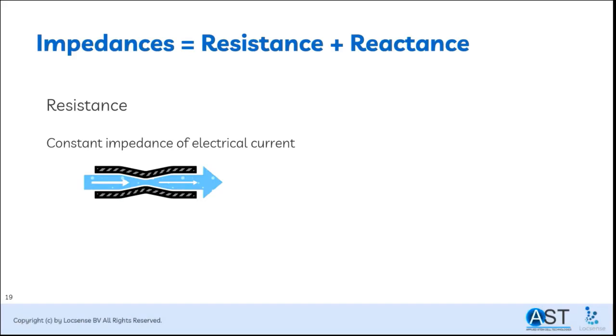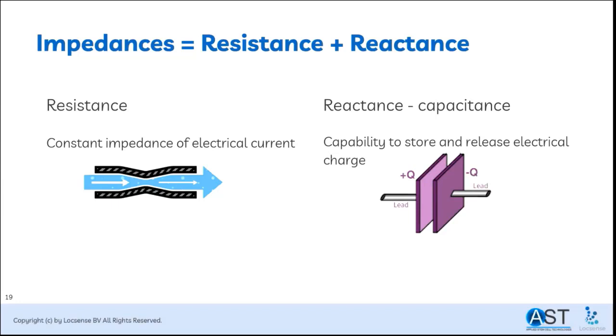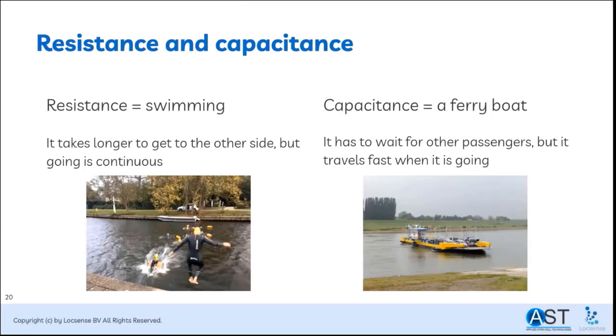TEER can be extracted from the impedance data, but total impedance is more than only TEER — it is the sum of the resistors and the reactances. Resistance is constant and always increases the total impedance. The most important reactance found in a biological cell layer is capacitance. A capacitance can hold and release electrical charge, and whether this impedes or facilitates the electrical current is dependent on the frequency. A resistance can be compared with swimming — it takes longer to get to the other side, but going is continuous. A capacitance can be compared to a ferry — you might have to wait, but once it takes off, it's traveling fast.